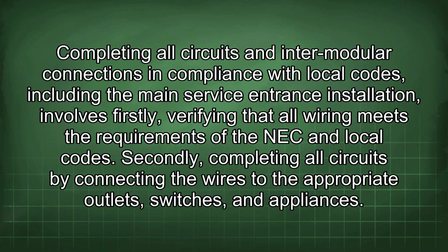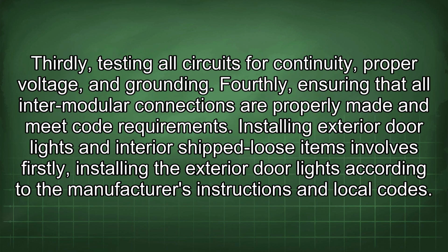Completing all circuits and intermodular connections in compliance with local codes, including the main service entrance installation, involves, firstly, verifying that all wiring meets the requirements of the NEC and local codes. Secondly, completing all circuits by connecting the wires to the appropriate outlets, switches, and appliances. Thirdly, testing all circuits for continuity, proper voltage, and grounding. Fourthly, ensuring that all intermodular connections are properly made and meet code requirements.